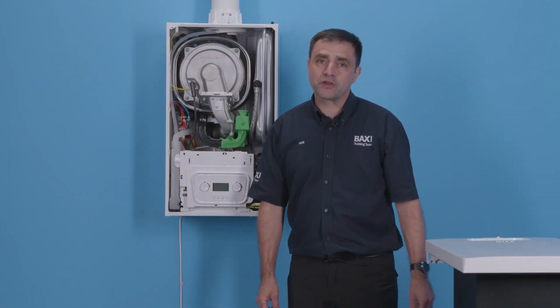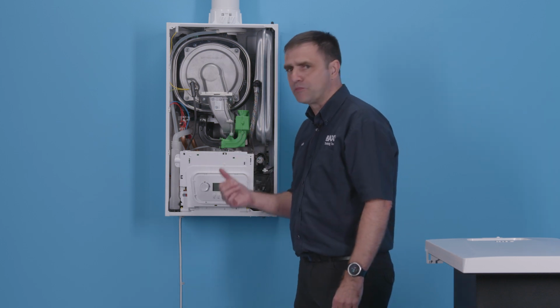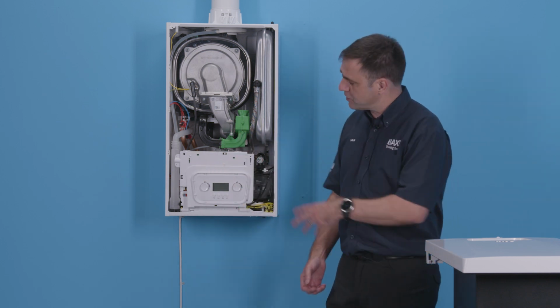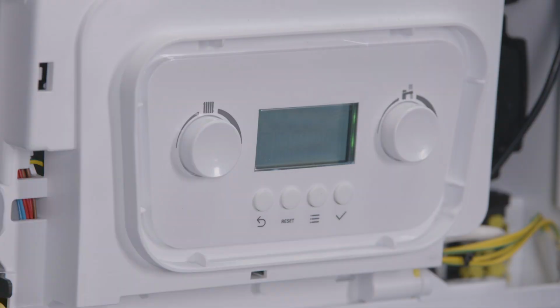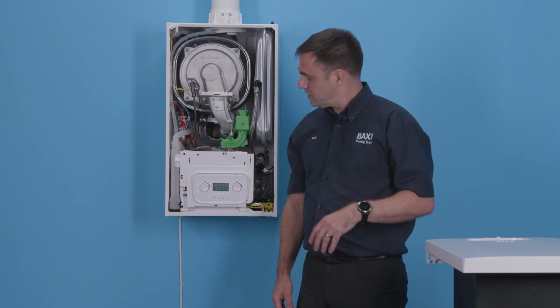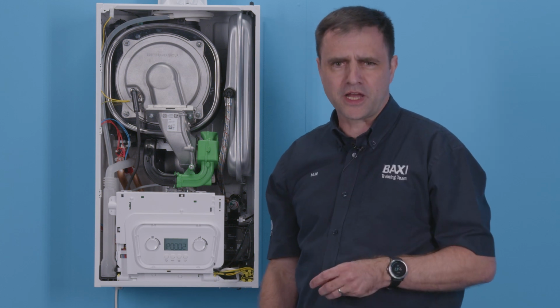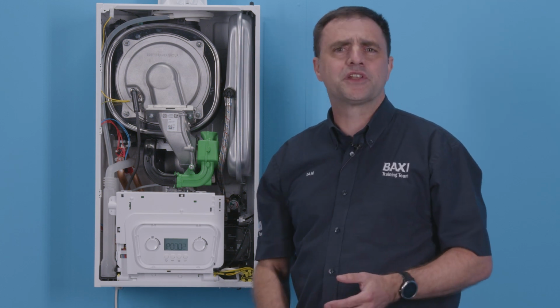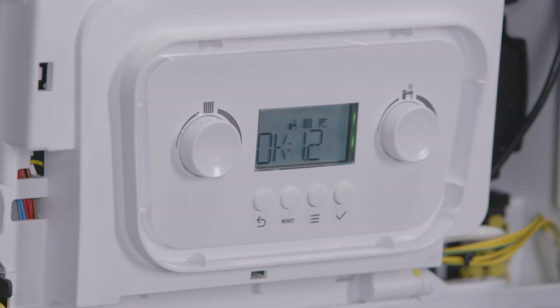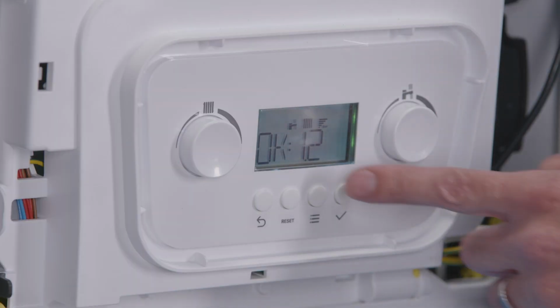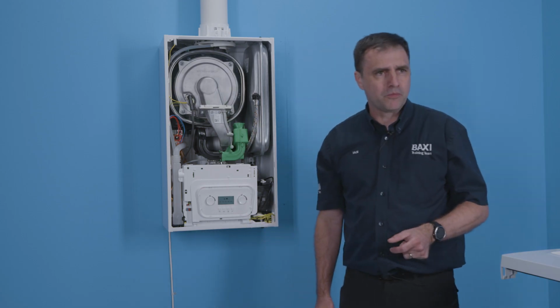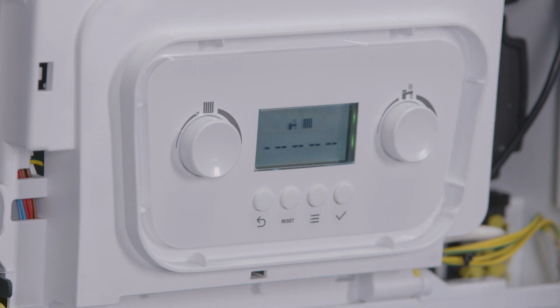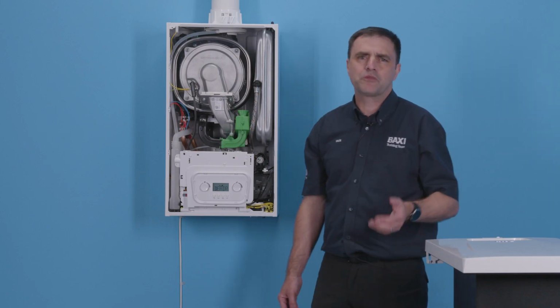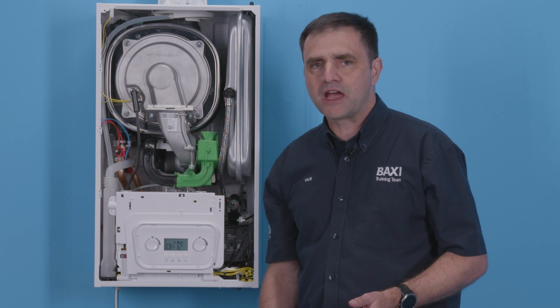Okay, so now I'm going to show you what you're going to see when you first power the boiler up and talk through some of the reasons we have to do deaeration. All the indicators illuminate on first power up. Then it moves through to the initialisation stage. It will show you the parameter number of the board, and it will go to the pressure, which must be over 1 bar. Once it's done that, it will move to a series of dashes. That's a countdown. It's a 5-minute deaeration.